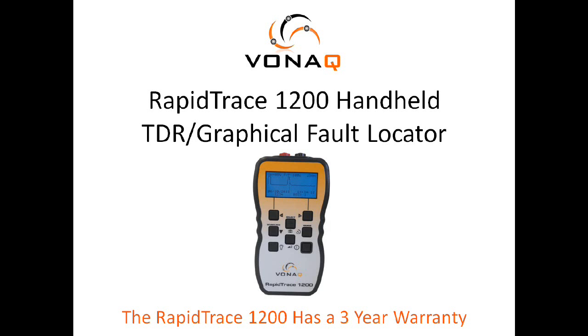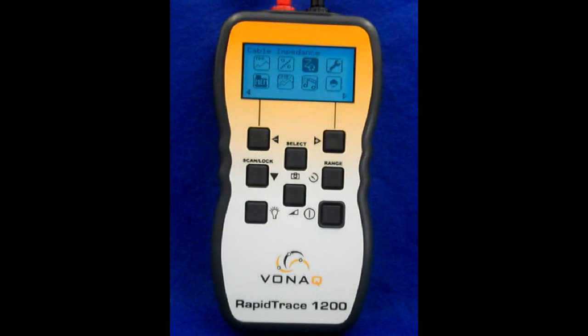In this short video you will see how accurate, quick and easy to use the RapidTrace 1200 is when locating the exact position of a cable fault. So let's take a look at how easy it is to configure the RapidTrace 1200 before we perform a TDR trace. Setting the cable impedance and velocity propagation.